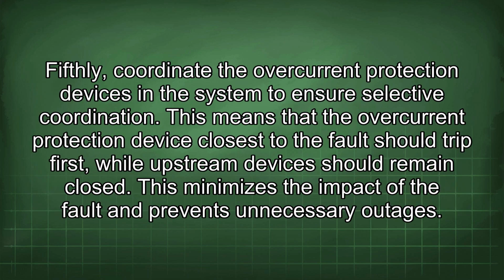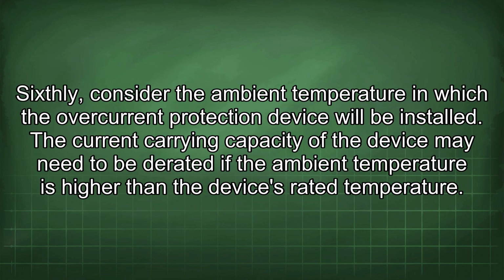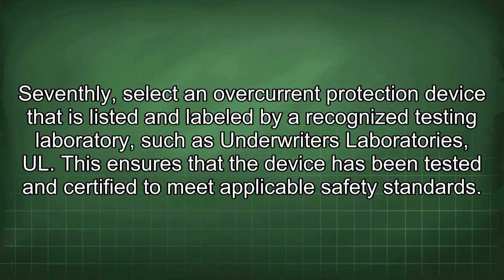Fifthly, coordinate the overcurrent protection devices in the system to ensure selective coordination. This means that the overcurrent protection device closest to the fault should trip first, while upstream devices should remain closed. This minimizes the impact of the fault and prevents unnecessary outages. Sixthly, consider the ambient temperature in which the overcurrent protection device will be installed. The current carrying capacity of the device may need to be derated if the ambient temperature is higher than the device's rated temperature.